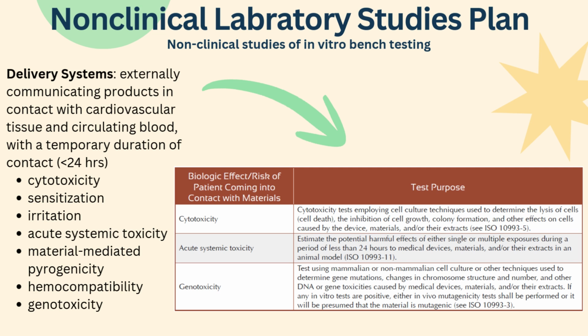So these specific evaluations would include cytotoxicity, sensitization, and irritation testing, again, to assess whether the materials are causing any local tissue or cellular damage during contact. We will also be doing acute systemic toxicity testing, which will evaluate the potential for short term systemic effects following its initial exposure, while the material mediated pyrogenicity assesses the risk of fever and other inflammatory responses that may be caused by the device materials. Because the delivery system contacts circulating blood, again, we will also be doing hemocompatibility testing, just to evaluate any risks of thrombogenicity and other coagulation responses.